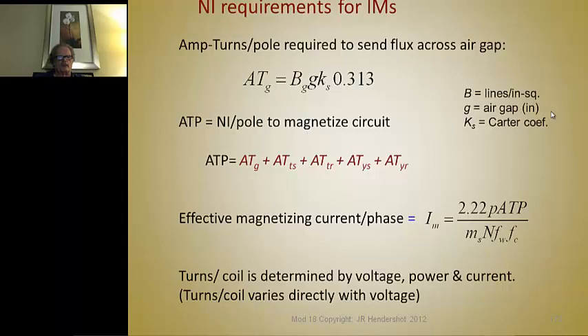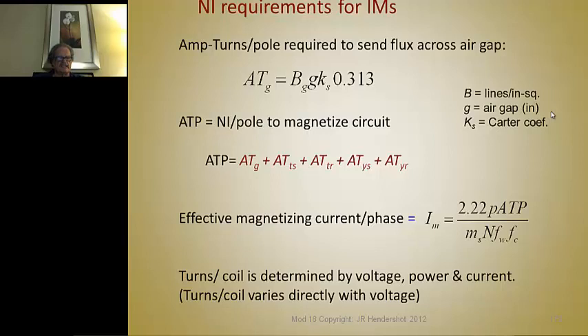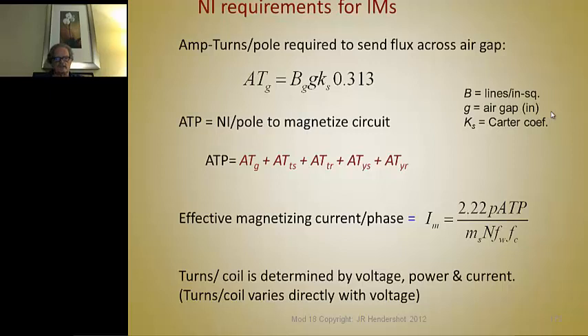The ampere-turns per pole to magnetize the circuit — that's not just for the air gap, but the ampere-turns required to magnetize the iron itself — is the sum of the ampere-turns required for each part of the circuit. The formula for effective magnetizing current per phase follows from this. The turns per coil is determined by the voltage, the power, and the current. Turns per coil vary directly with voltage: the higher the voltage, the more turns you have.